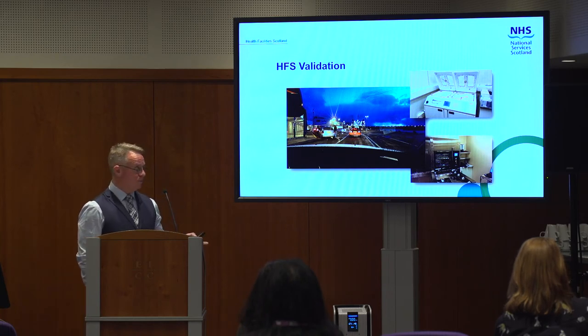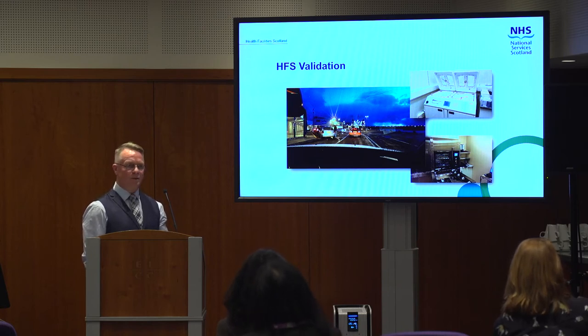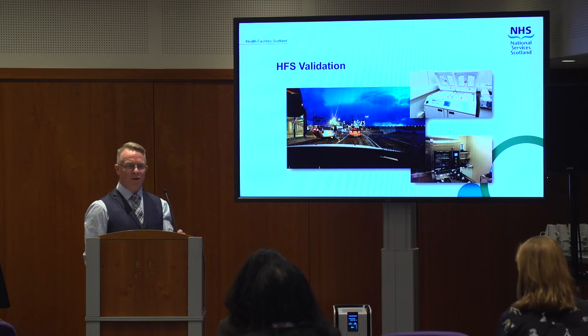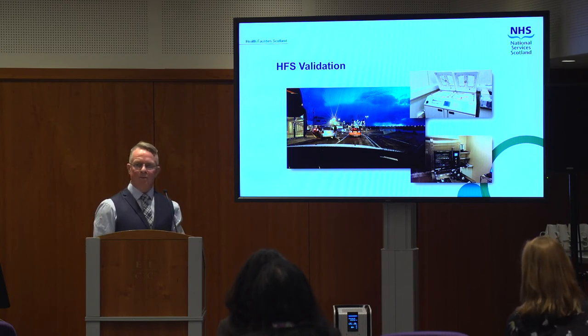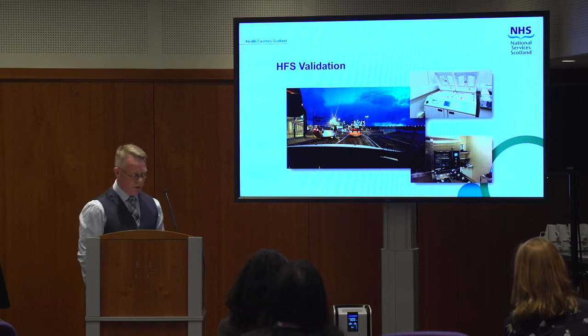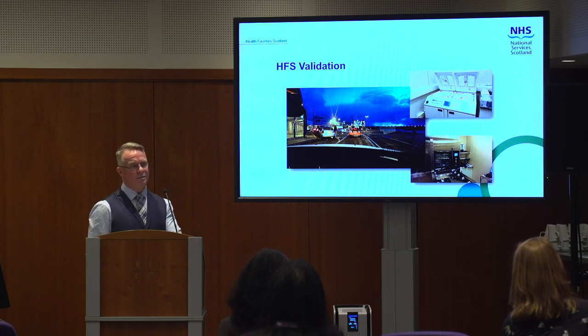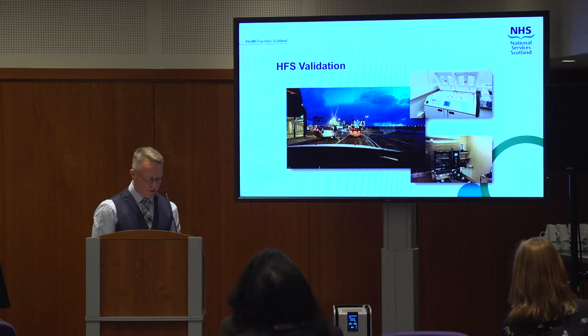Planning some of these jobs is a bit like a military campaign at times. Sometimes hospitals would rather you visited and did all the machines on the same visit, so there's an economy of scale — we might double up in cars, cutting back on travel. We've got a lot of test equipment to transport, but that also means you might have spare kit — if somebody's kit develops a fault within the testing window you've hopefully got backup. Many samples, especially in endoscopy — water samples and microbiological stuff — have to be back on the Friday to get into the testing house within tolerance and within the control window.